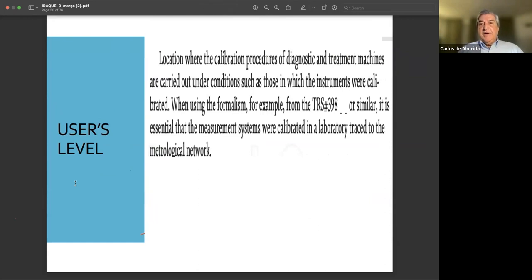The location of the SSDL varies in each country, but that's where you should have all the standards for diagnostic and treatment machines, and also the reference to calibrate the well chambers used in nuclear medicine. And what they do is use the formalism of the TRS 398 or TG 51, like the Americans do, in a very standardized way, in a reference condition, so everybody will be measuring the same way. Next one.